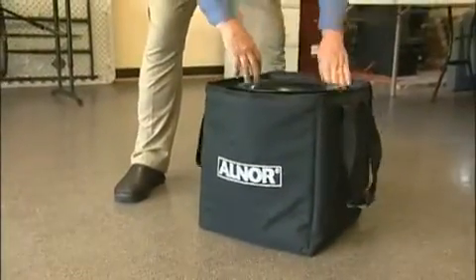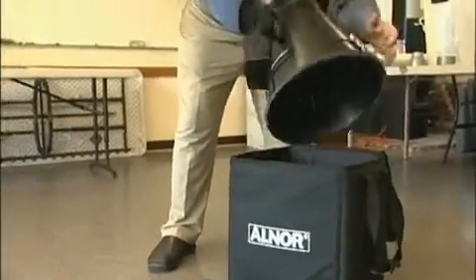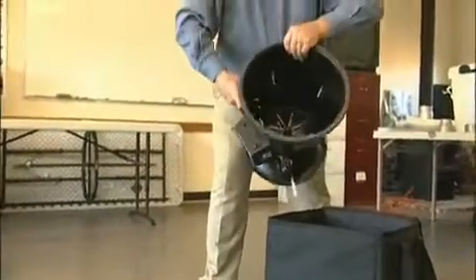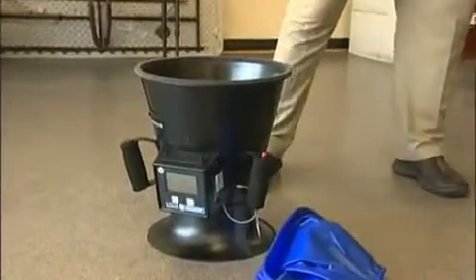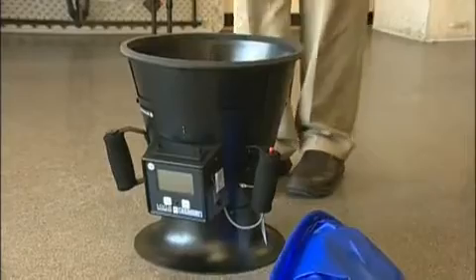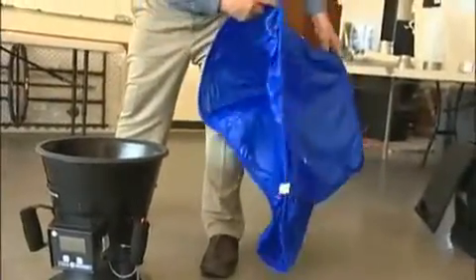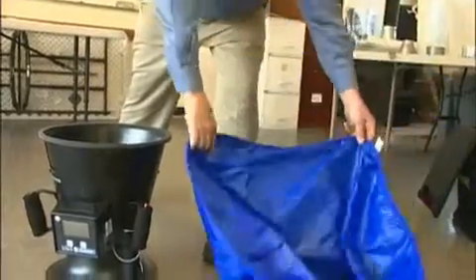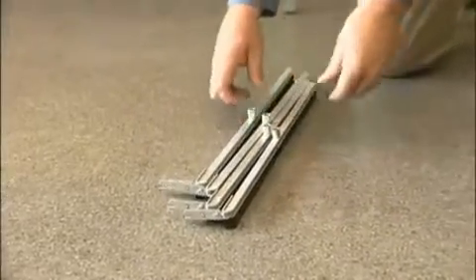The Alnor flow hood comes in a case that's padded, about 18 inches cubed. It has a sleeve to reach up to the ceiling from the device and the actual flow measuring device itself. This operates using a pitot tube array that measures the pressure of the air flowing through it so it can actually calculate what the volume is. The sleeve is made of a nylon type fabric and it's supported by a frame that we have to assemble that is two feet square.